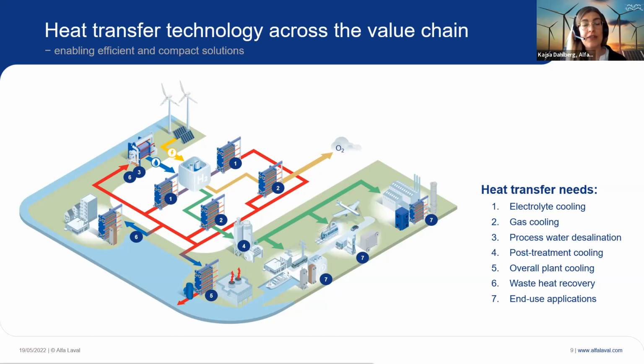Focusing on the electrolyzer and the waste heat generated: the electrolyte in the electrolyzer is cooled off by heat exchangers next to it, and the hydrogen and oxygen produced are also cooled off by one gas cooler each before further post-treatment. This heat recovered in these four heat exchangers can either be let out into surrounding water or air, used for industrial or district heating needs, or integrated back into the process itself to produce fresh water for the electrolyzer. As this is a rather low temperature process, 50 to 80 degrees Celsius, it's difficult to find a good offset for this heat.